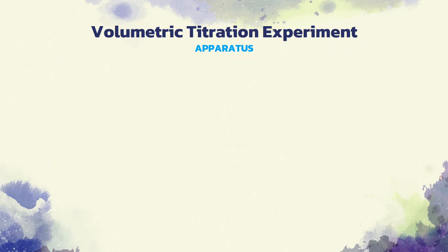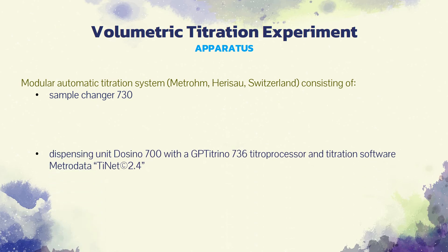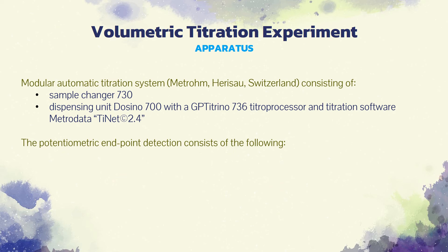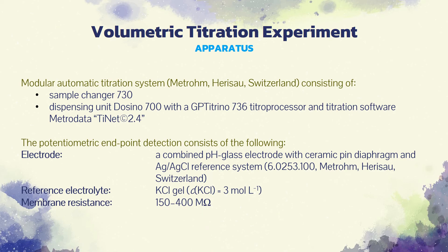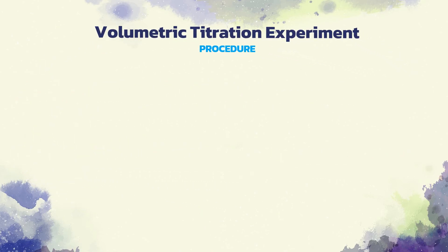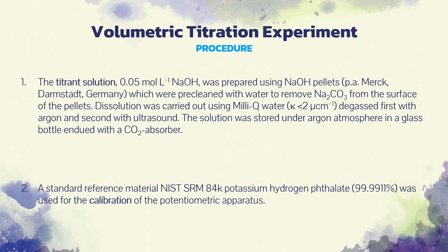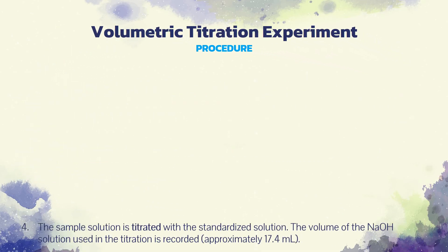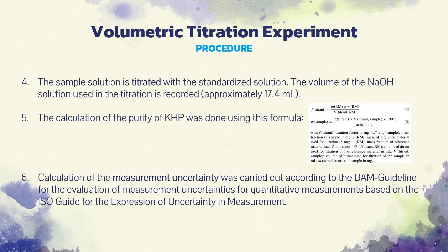For the volumetric titration experiment, titrations were carried out using a modular automatic titration system consisting of a sample changer and a dispensing unit. For potentiometric endpoint detection, a combined pH glass electrode and silver-silver chloride reference system was used. The experimental procedure involves the preparation of the titrant, calibration of the apparatus, drying of the sample, titration of the sample, and calculation of purity and measurement uncertainty.